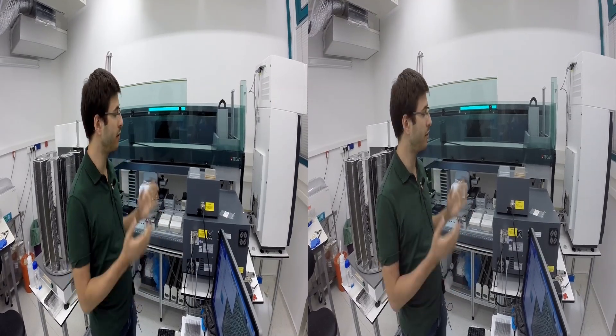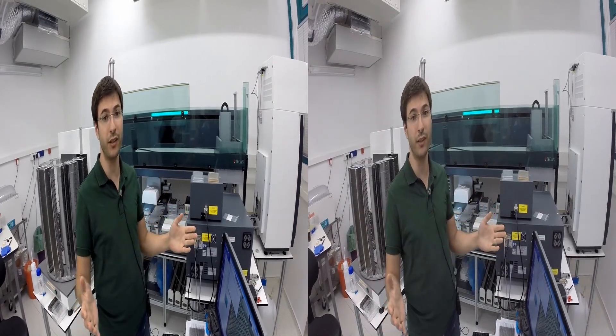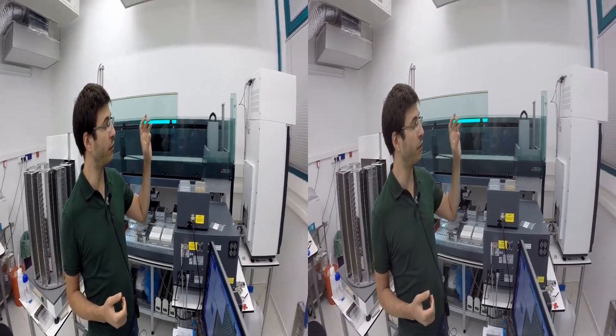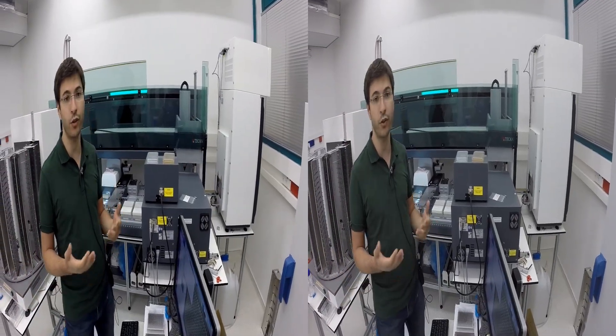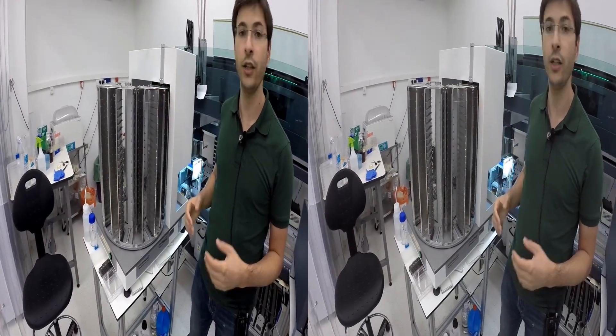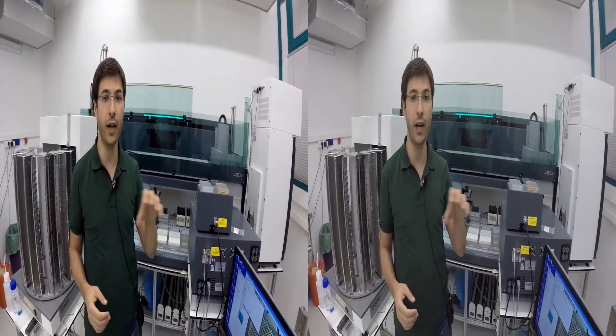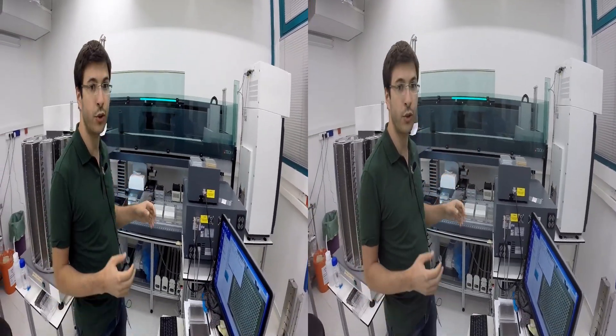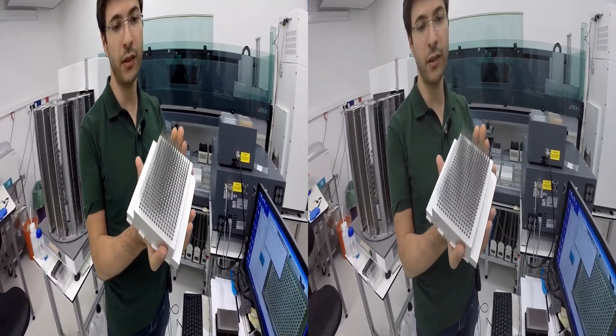Hi again, I'm Emmanuel Levy, and this is a robotic setup that we use to measure protein-protein interactions and protein colocalization in living yeast cells. Because these two quantities involve pairs of proteins — if you have a thousand proteins, you have a million possibilities — we need to be able to work at very high throughput. For this, we have an automated incubator, a plate reader that can read fluorescence, luminescence and optical density, and a carousel that can accept about 200 plates. We will soon receive a spinning confocal microscope that will be linked to the robot through a robotic arm. At the center, we have a liquid handler that can transfer plates from one instrument to another. When we work with liquids, we usually work in 384 format.